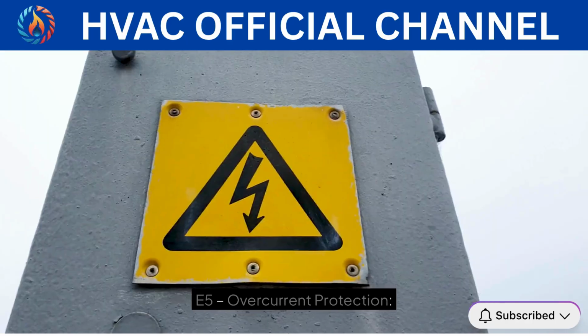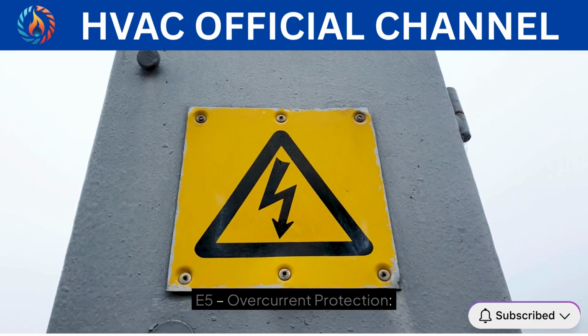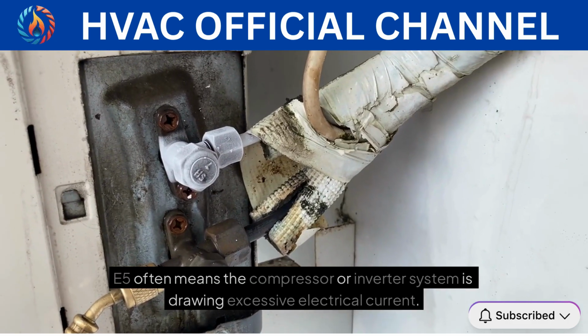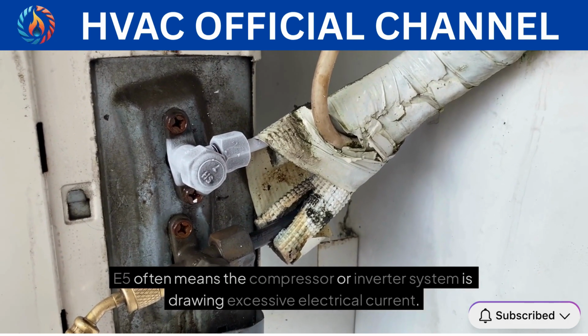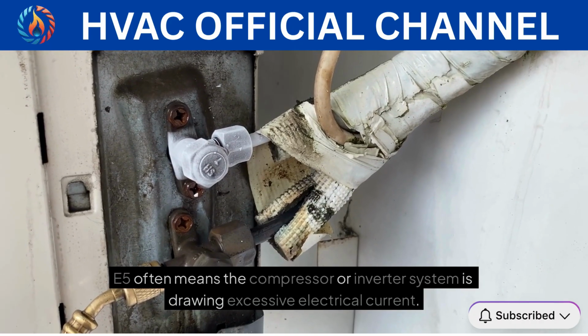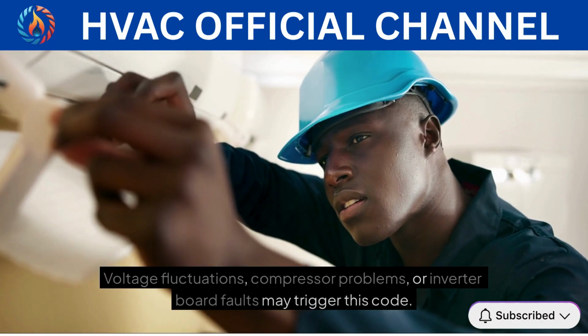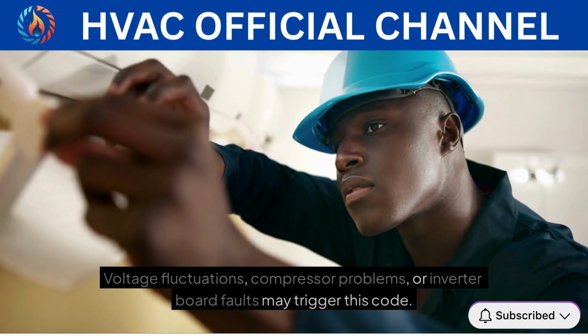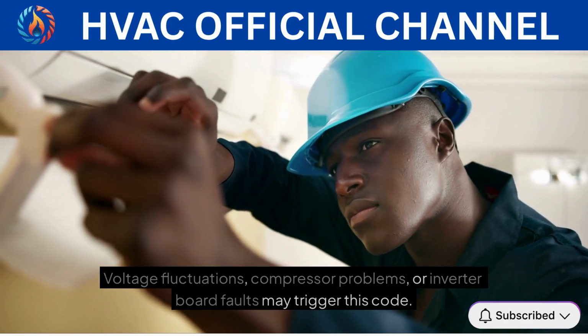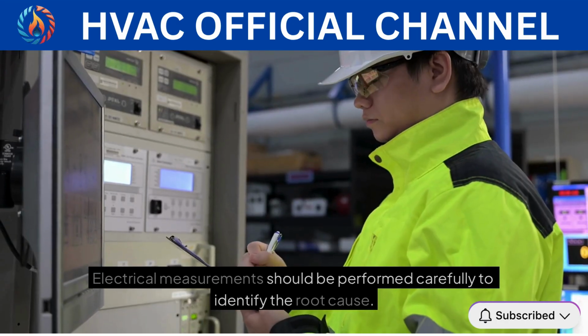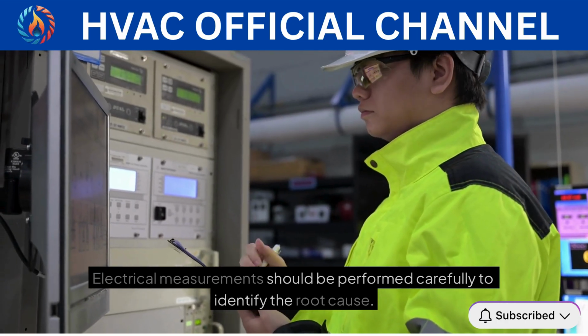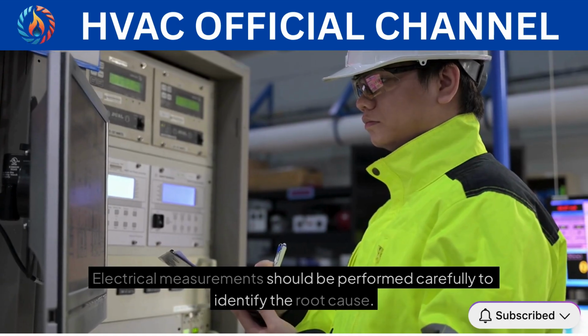Error code 5, E5, overcurrent protection. E5 often means the compressor or inverter system is drawing excessive electrical current. Voltage fluctuations, compressor problems, or inverter board faults may trigger this code. Electrical measurements should be performed carefully to identify the root cause.